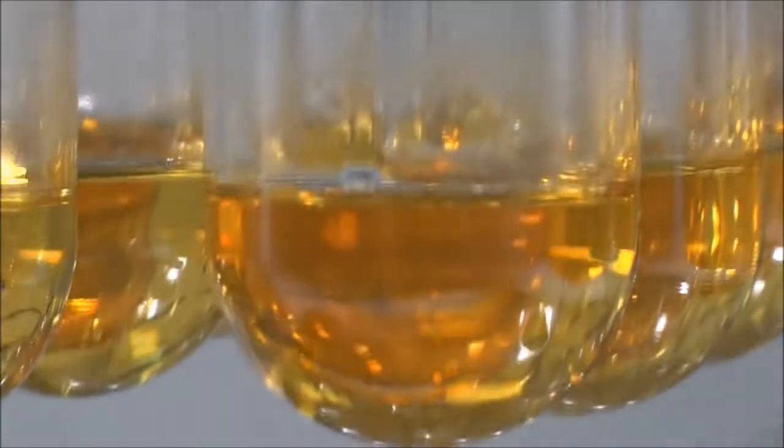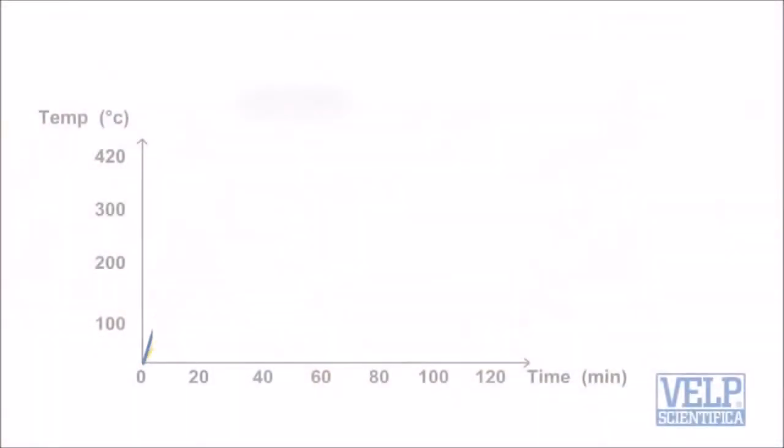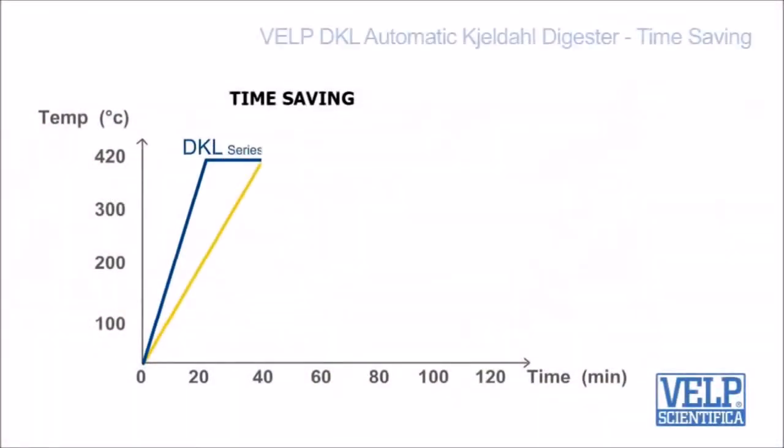The overall processing time is greatly reduced as the block takes only 22 minutes, about half the usual time, to reach the operating temperature before starting the full digestion process.